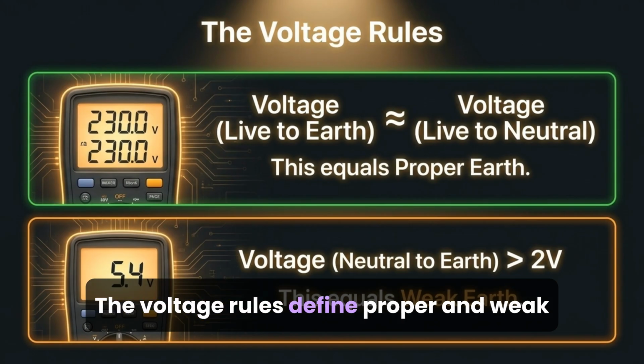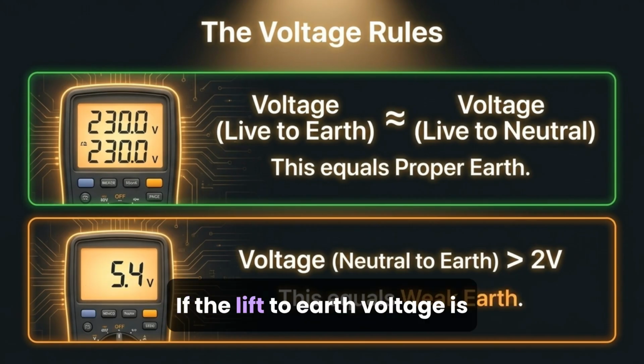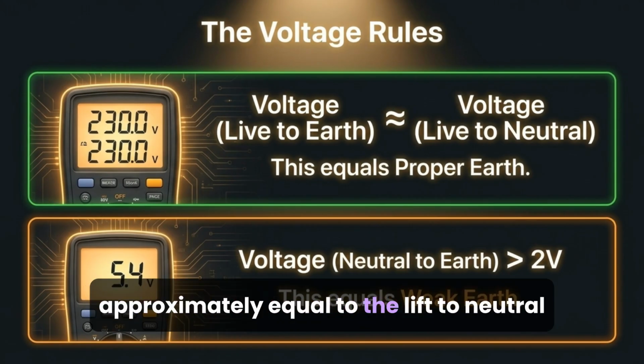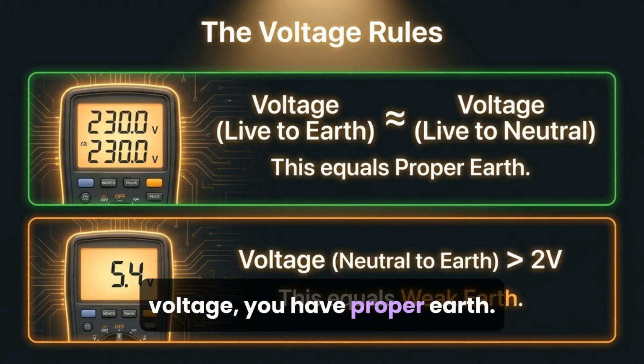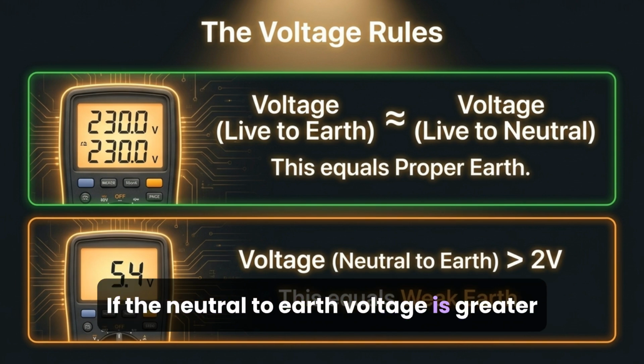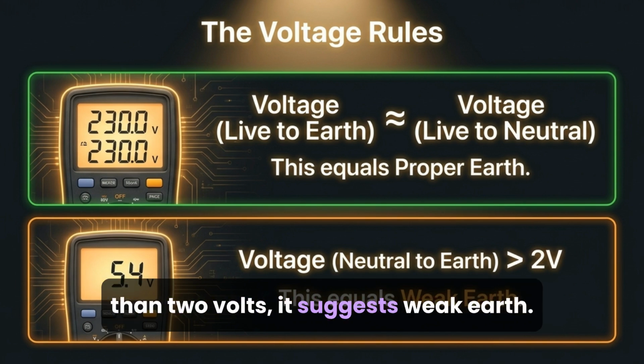The voltage rules define proper and weak earth. If the live-to-earth voltage is approximately equal to the live-to-neutral voltage, you have proper earth. If the neutral-to-earth voltage is greater than 2 volts, it suggests weak earth.